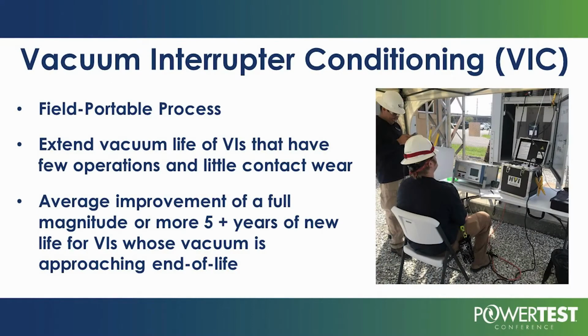This is best suited for interrupters that have little wear, have no mechanical failures, haven't been through an extreme fault, don't show any signs of wear. Now, when you get a breaker past its wear limits, no amount of conditioning will solve this problem. When a breaker gets past its wear limits, the actual wipe springs can no longer hold the interrupter closed properly, and the popping forces will cause all kinds of problems for you. So you really need to keep these interrupters in the middle of the pressure band or lower, and once you get to the wear limits, you need to replace them.